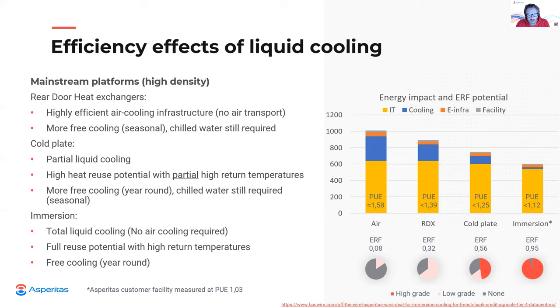Immersion is about literally immersing the IT systems in the dielectric fluid. And this holistic type of cooling, which captures 100% of IT energy, can operate with elevated temperatures for the full platform. This also means that immersion enables year-round operation with free cooling strategy. The elevated temperature capabilities also have significant impact on the potential energy reuse factor. The shown pie charts give an indication of achievable ERF with different liquid cooling strategies.